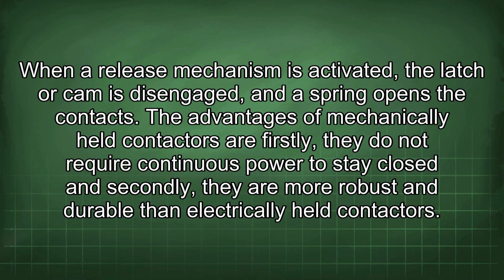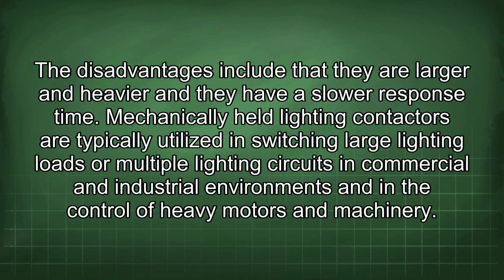The advantages of mechanically held contactors are, firstly, they do not require continuous power to stay closed, and secondly, they are more robust and durable than electrically held contactors. The disadvantages include that they are larger and heavier, and they have a slower response time. Mechanically held lighting contactors are typically utilized in switching large lighting loads or multiple lighting circuits in commercial and industrial environments and in the control of heavy motors and machinery.